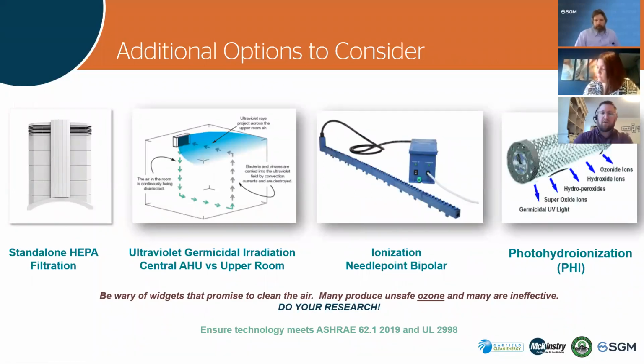So the next category is some additional options to consider. And these are most likely addressing some unique spaces or some spaces where we're not able to get the amount of filtration, the amount of outside air we need, though we have had plenty of clients just apply some of these across the board as their main strategies. So the first is standalone HEPA filtration, absolutely effective per ASHRAE. And readily available. The next is UVGI or ultraviolet germicidal irradiation, also recognized by ASHRAE as effective. This is a little more challenging application-wise.